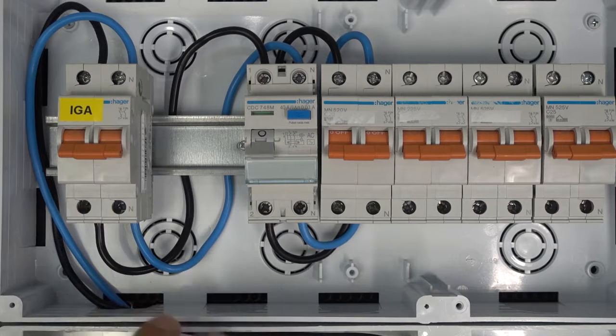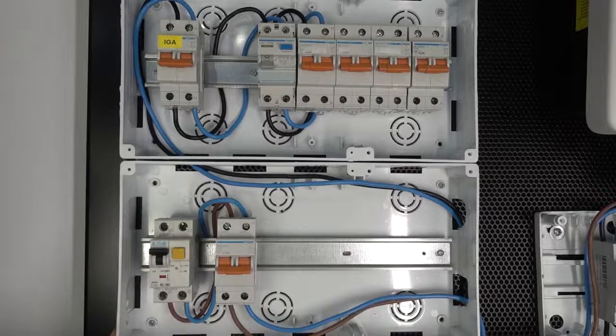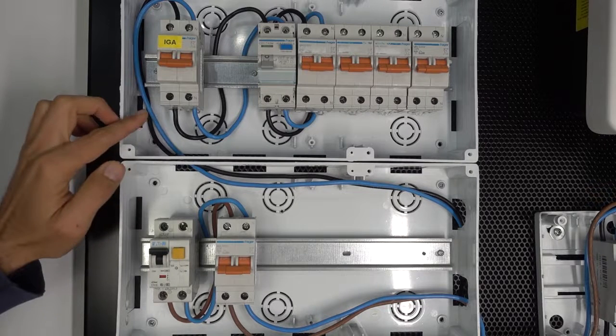So starting from this electrical panel, we are going to add in the lower part some protections where we are going to connect the grid inverter. Here in the lower part of the general switchboard of the house, we have connected a differential switch and a thermal magnetic breaker that will go to the inverter. The only thing left to do is to connect it downstream of the main circuit breaker.